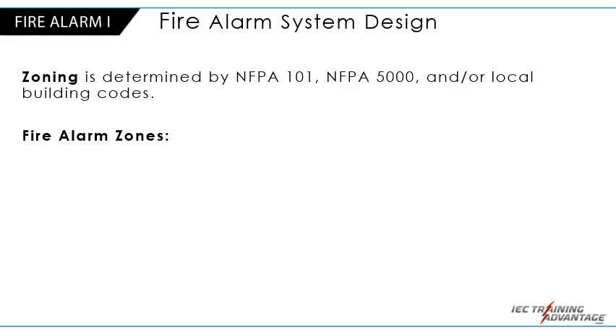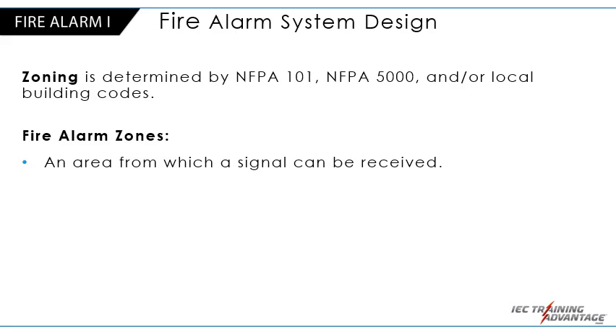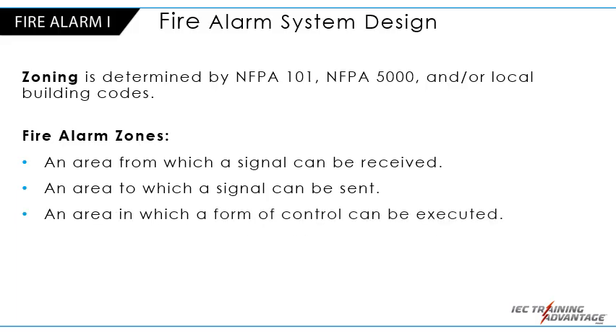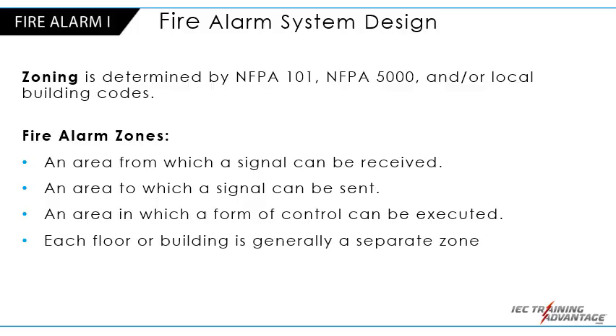When it comes to zoning, this is determined by NFPA 101, NFPA 5000, and/or local building codes. This zoning is required to know what type of devices and what type of coverage per occupancy is required. Fire alarm zones are an area from which a signal can be received, an area to which a signal can be sent, or an area in which a form of control can be executed. Each floor or building is generally a separate zone, and each building is zoned separately.